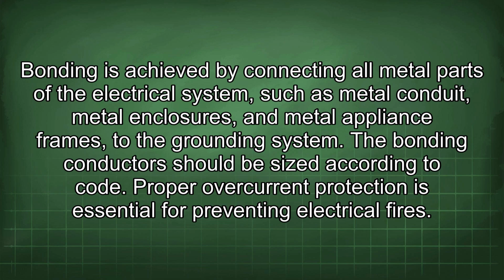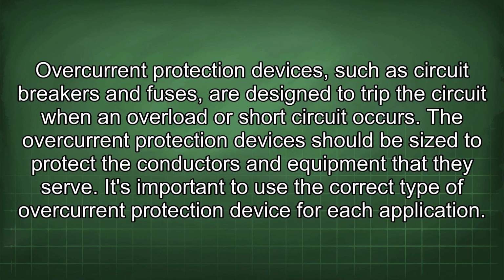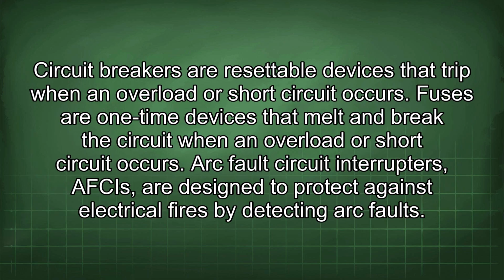Proper overcurrent protection is essential for preventing electrical fires. Overcurrent protection devices, such as circuit breakers and fuses, are designed to trip the circuit when an overload or short circuit occurs. The overcurrent protection devices should be sized to protect the conductors and equipment that they serve. It's important to use the correct type of overcurrent protection device for each application. Circuit breakers are resettable devices that trip when an overload or short circuit occurs. Fuses are one-time devices that melt and break the circuit when an overload or short circuit occurs.